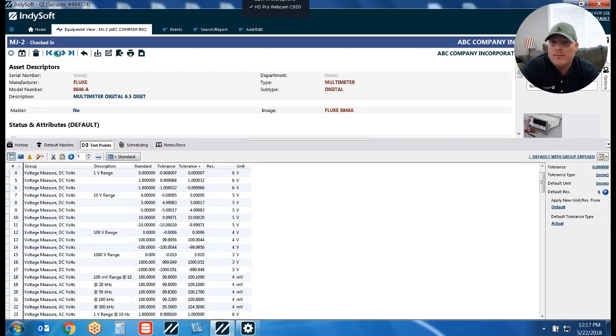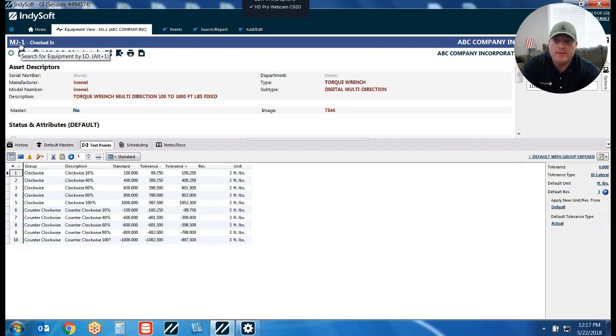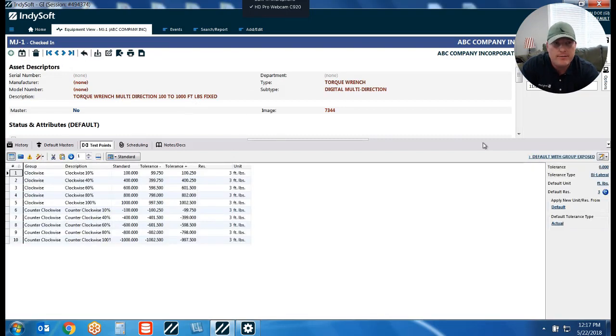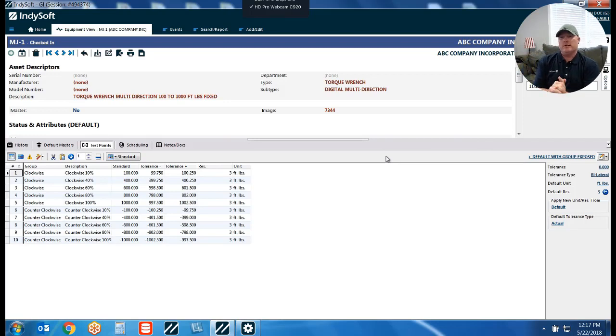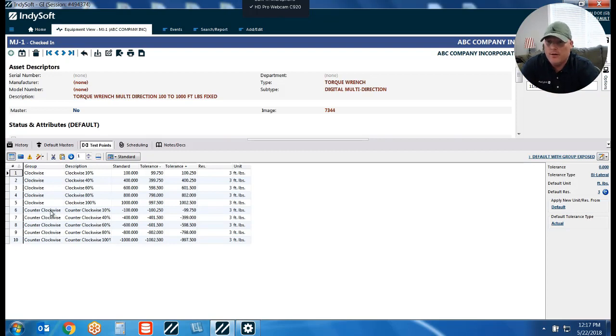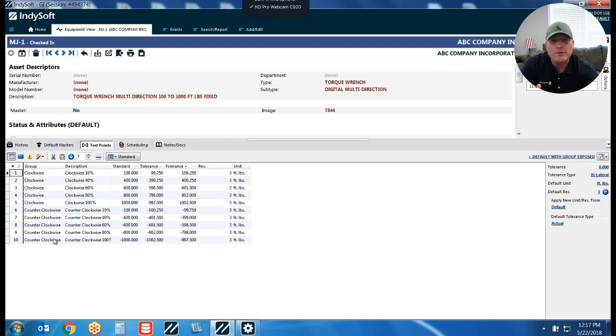The first one I want to show you is a piece of equipment I've previously set up — a torque wrench. This is a scenario that came up in a demo last week, which is what sparked me to do this video. When we look at our test point grid, you're going to see two different groups of test points: I've got my clockwise group and my counterclockwise group. By having those set up, we can create a scenario where when you launch your calibration event, the software gives you a pop-up box asking which set of test points you want.